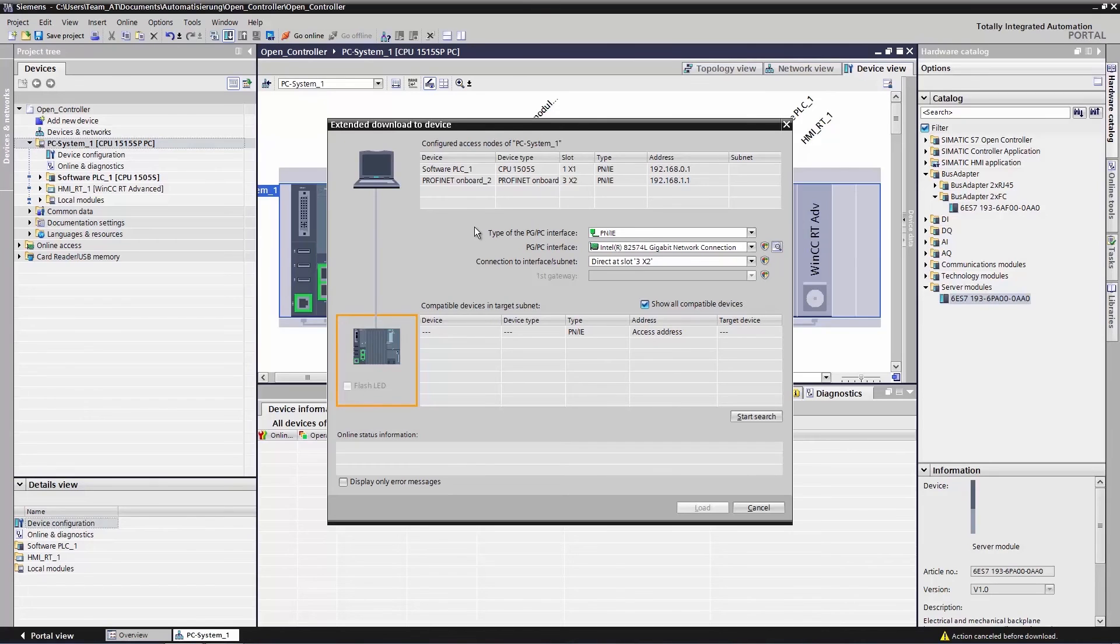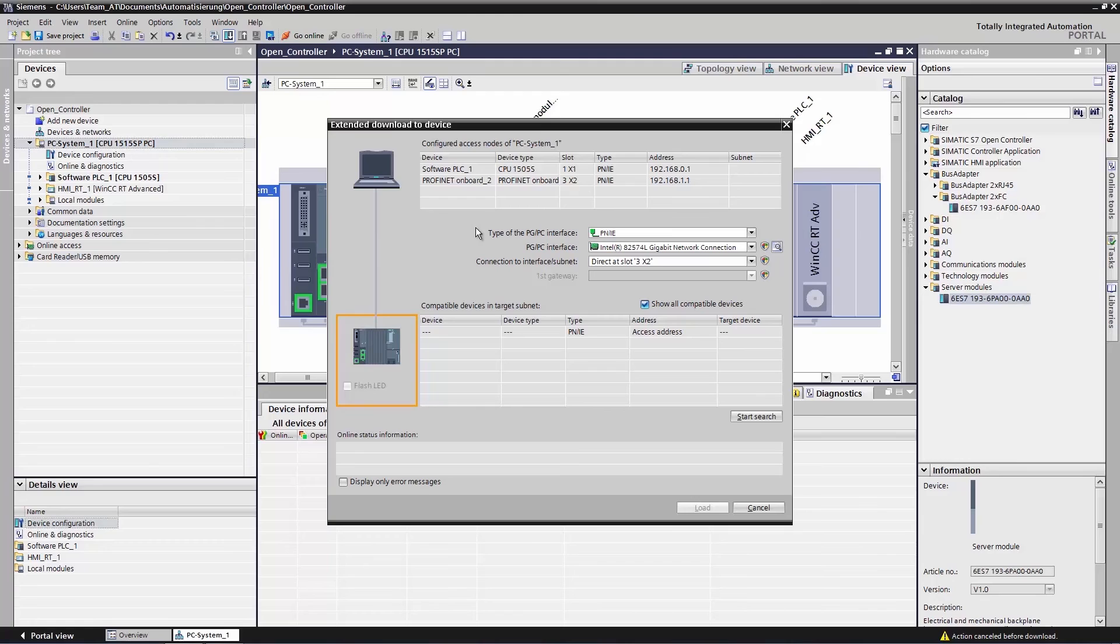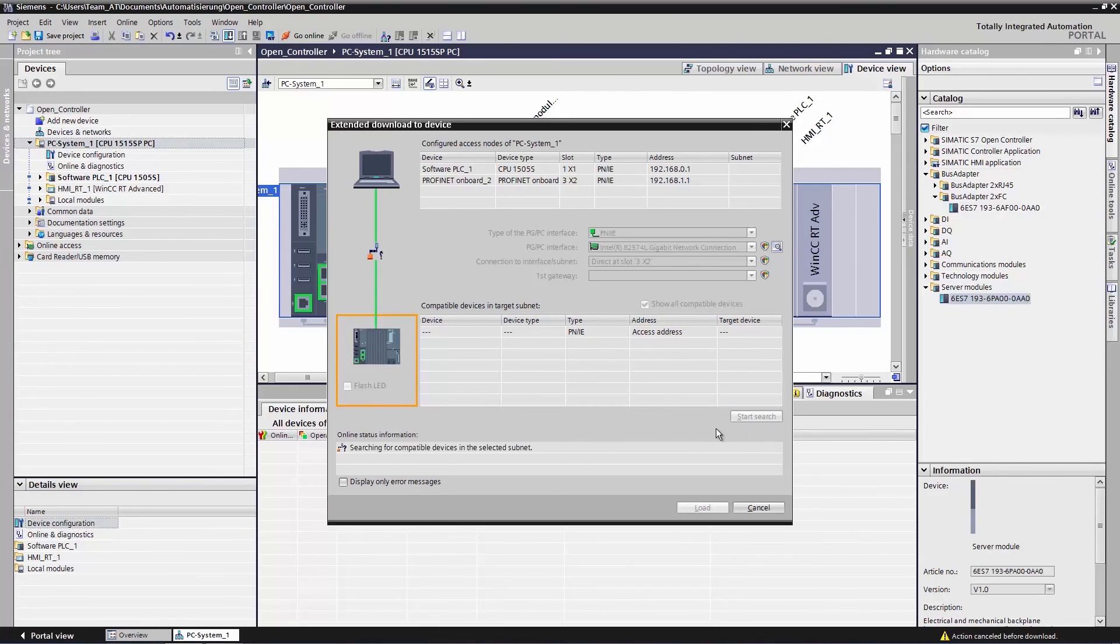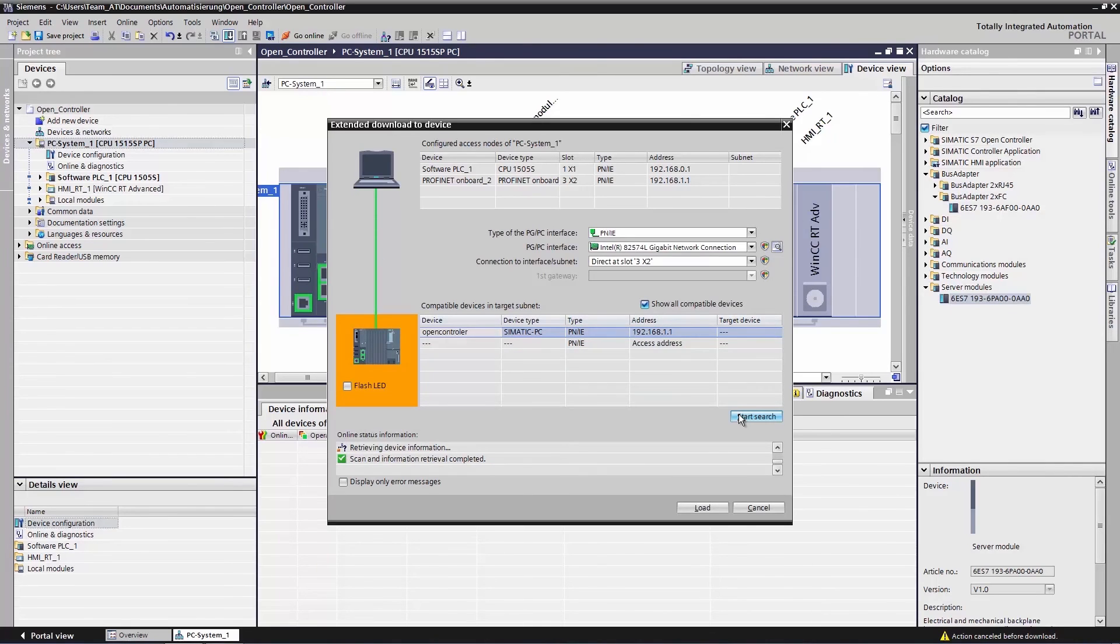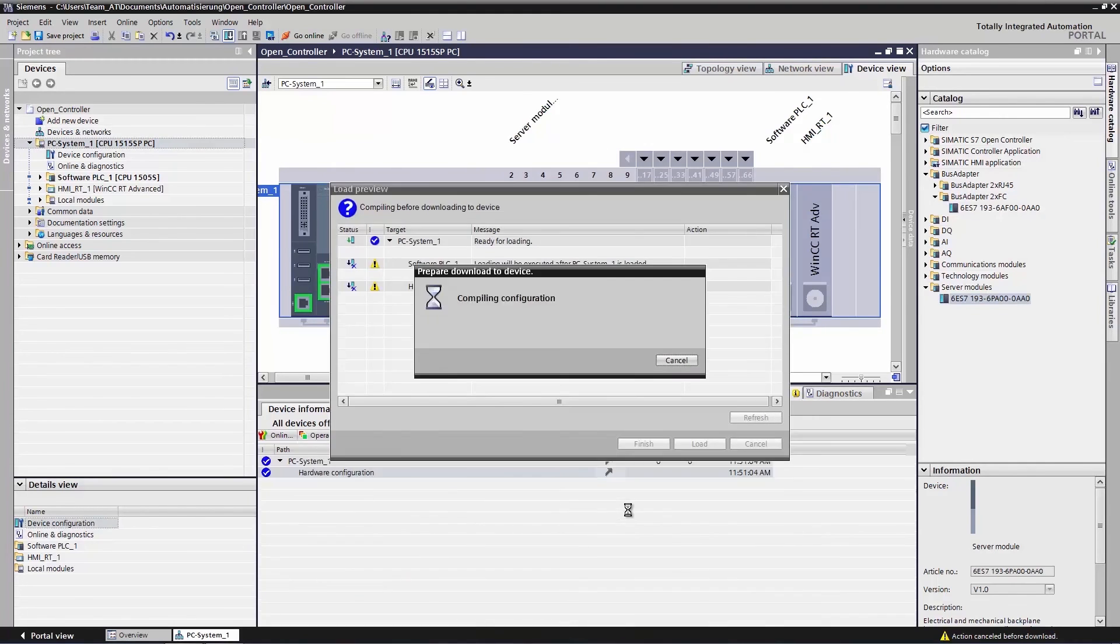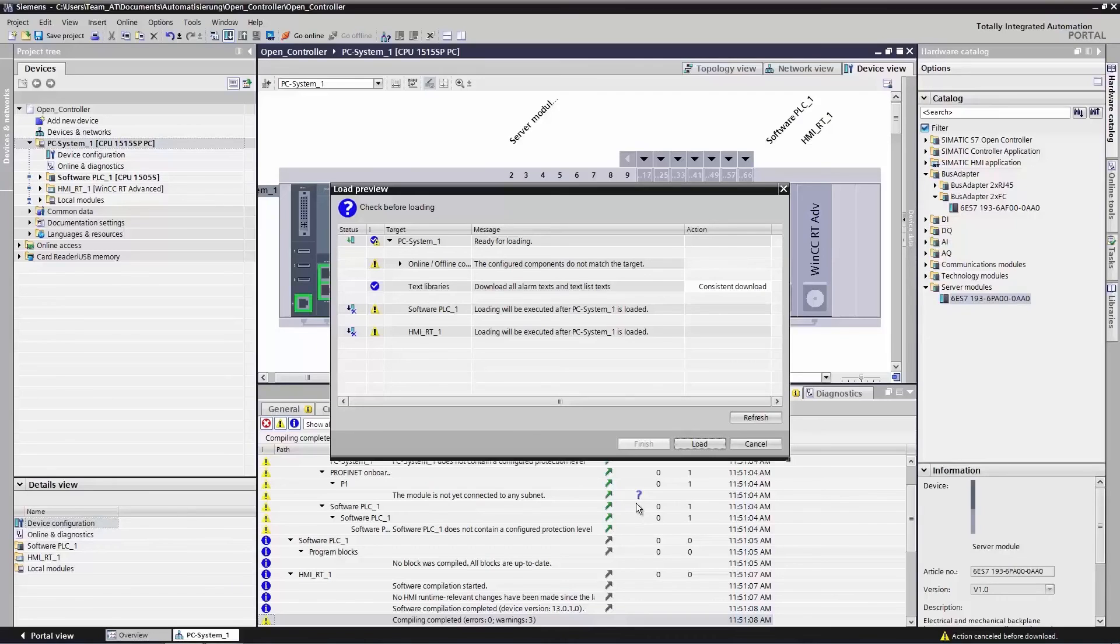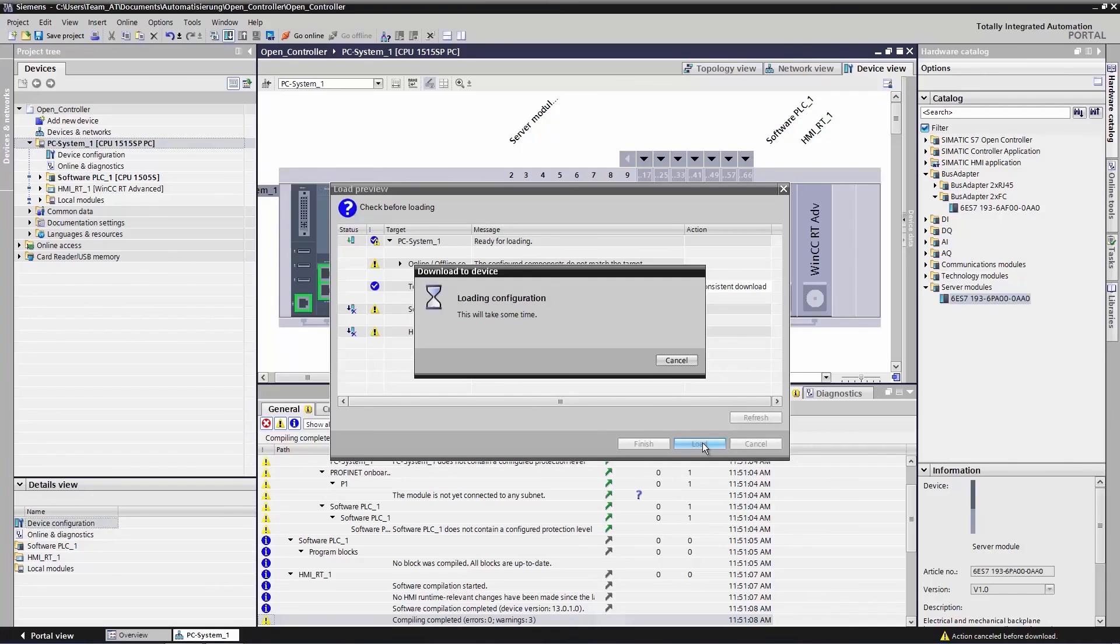In the download menu, we set our connection type, specify the interface with the PG, which should be in the same IP address range as the open controller. And here, right at the bottom, we specify the X2 interface on the open controller. We then start a search and find the open controller as our communication partner. We click load and then the TIA portal will begin to compile the project and prepare the download. We go back to load once again.